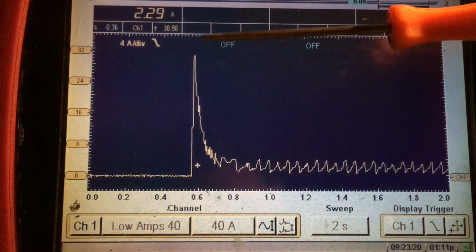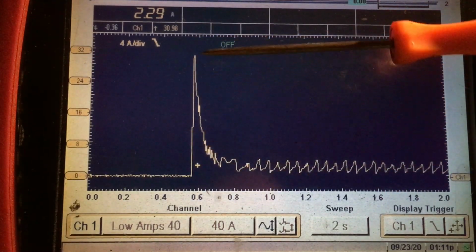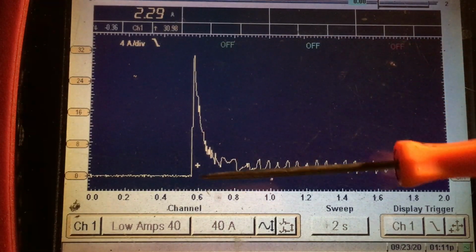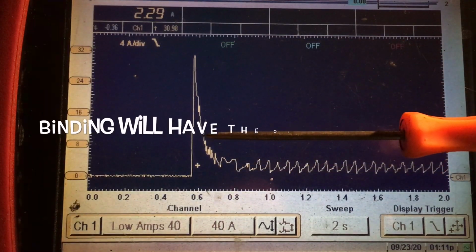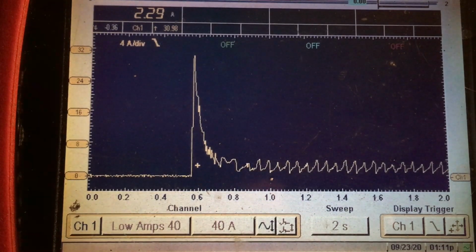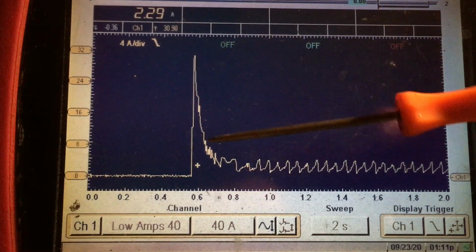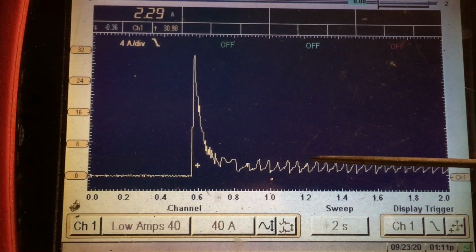But look at the profile of the inrush current. This looks like the Empire State Building to me. It goes straight up and pretty much straight down. This is a sure sign that there's no flywheel effect on the motor. The inertia has been overcome very quickly, and the running speed has been attained very, very quickly. If you think that through, that is synonymous with a scenario of a mechanical disconnect. The motor is not driving anything, or at least very little with respect to its load.